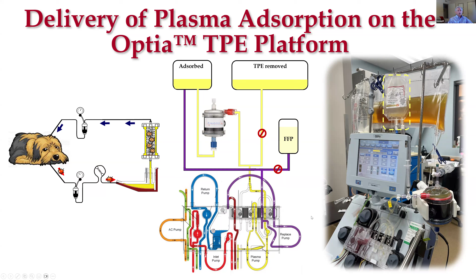On the Prismax, we thought, well, geez, how would we do this? We can put a plasma separator on here. We can get the plasma out, run that through our sorbent. But the problem on the Prismax is that you've got to satisfy the requirement that every drop of fluid that comes out of the plasma into the plasma waste bag has to be matched by exactly the same amount of volume that comes out of the replace bag. So you've got that constraint that these two bags have to be matched, and you can't just do the plasma separation without having some kind of a replacement going back to the patient.